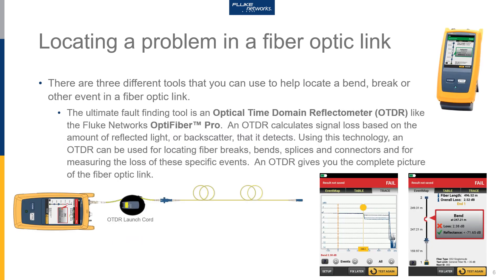If you want to consider it, the ultimate fault-finding tool for fiber optic links is the Optical Time Domain Reflectometer, or OTDR — from Fluke Networks, this is the OptiFiber Pro. An OTDR calculates signal loss based on the amount of reflected light, or backscatter, that it detects. Using this technology, an OTDR can be used for locating fiber breaks, bends, splices, and connectors with issues, and it will measure the loss of these specific events.